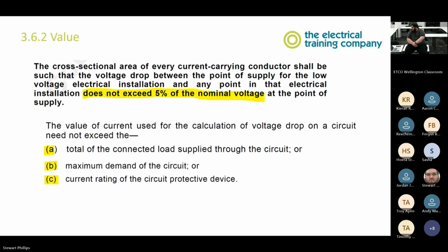Cool. So we must make sure that we have a sufficient cross-sectional area so that the electrical installation does not exceed 5% of the nominal voltage at the point of supply. So that's for volt drop. So we cannot allow more than 5% volt drop at any point in the installation, versus the voltage at the point of supply. That's why sometimes we increase the size of the conductor, even though we're not carrying much current. Over such a distance, we're going to get volt drop. You guys will learn a lot more about this in year 3.